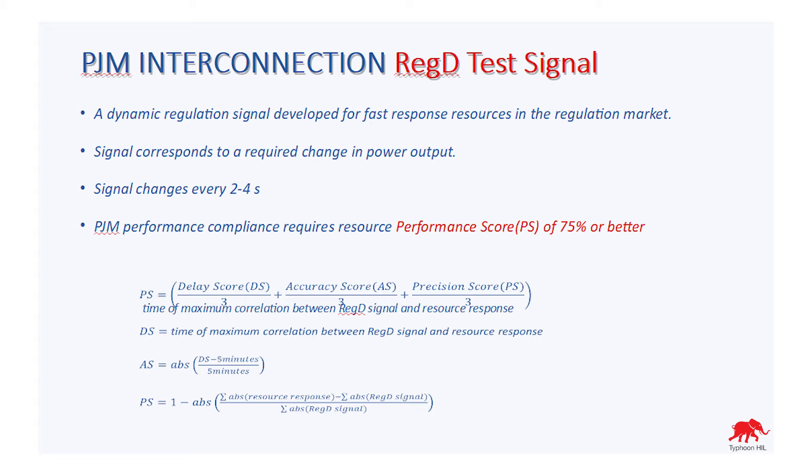And PJM performance compliance requires resource performance scores of 75% or better. The performance score is computed by taking into account the correlation of the power outputs of the distributed energy resources and the Reg D test signals, and also the delay in response of these resources. And the performance score is computed according to this formula.